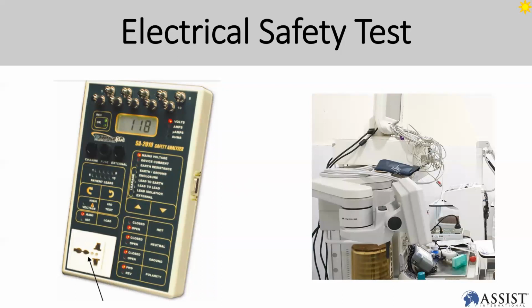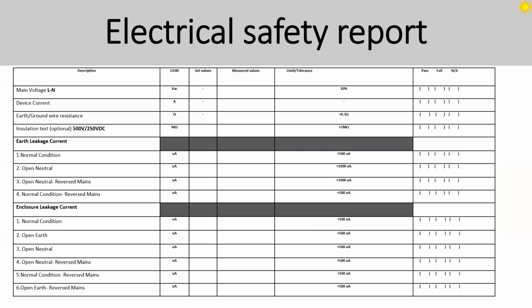Electrical safety is very important because you need to check the equipment is safe to use on the patient. So you need to check, is the equipment electrically safe, all that. So you need to do electrical tests during the PM. So when you talk about report, normally it depends on the class of device. You've got class 1 device, class 2, but most of the ventilators or anesthesia machines that you see are class 1 devices. So you need to do all these tests, except patient applied circuit.